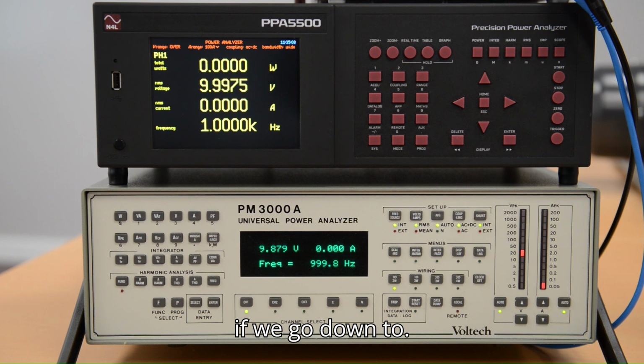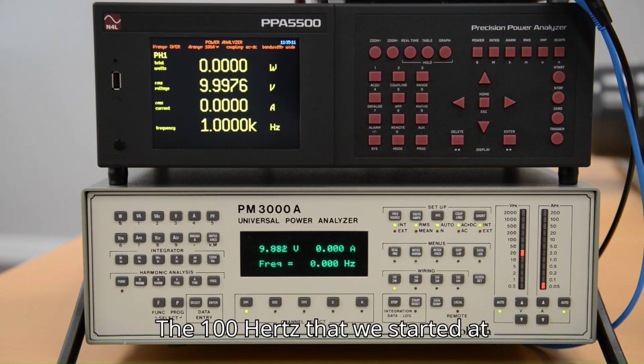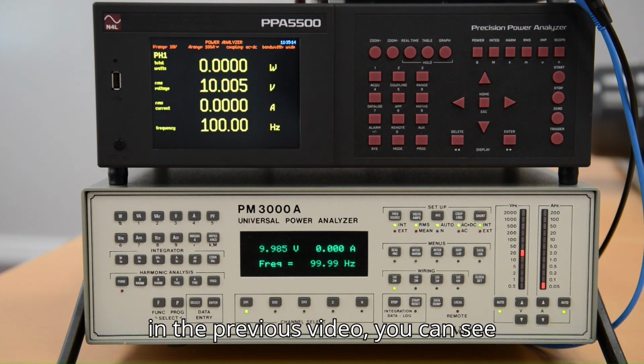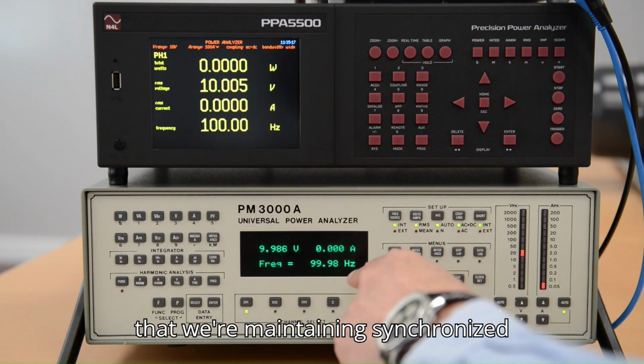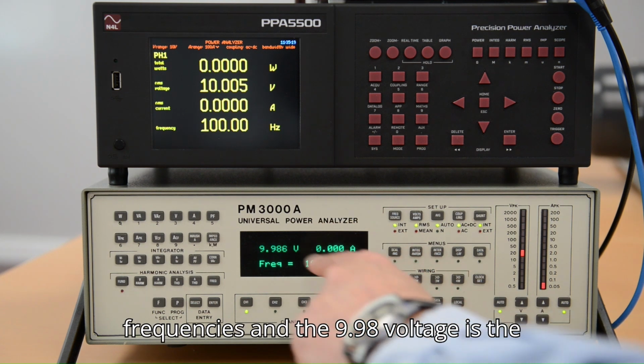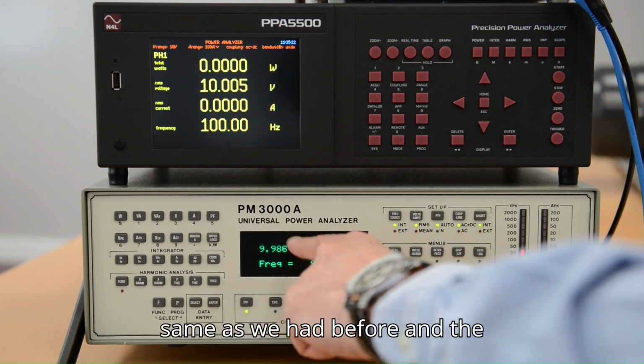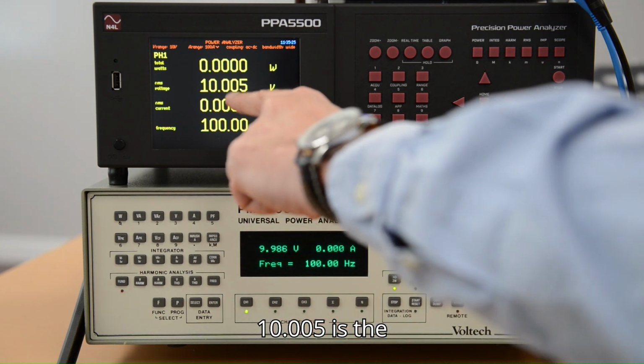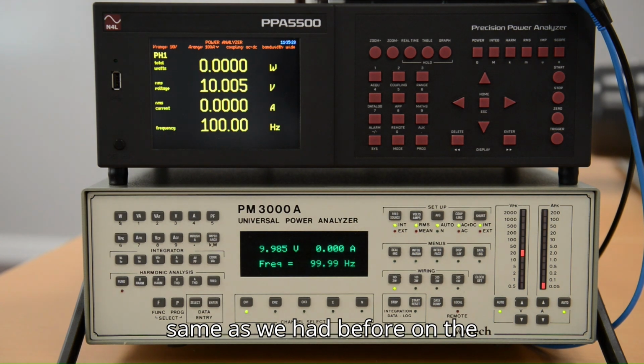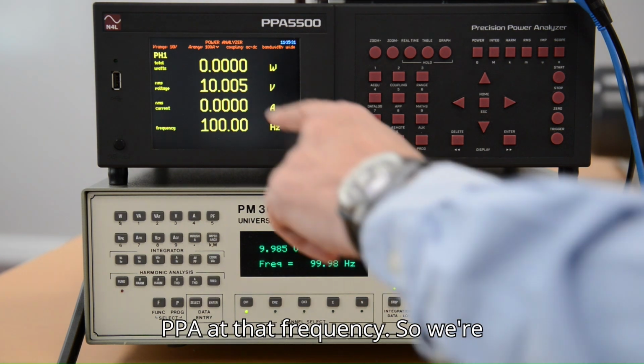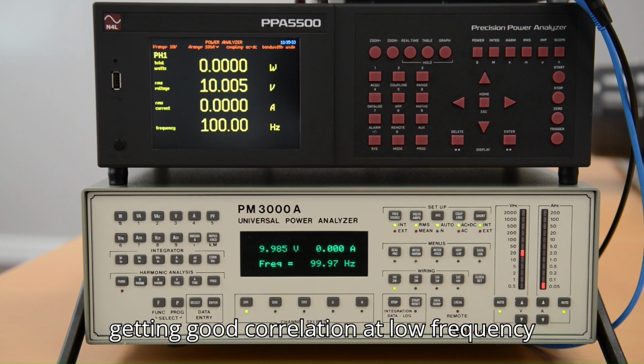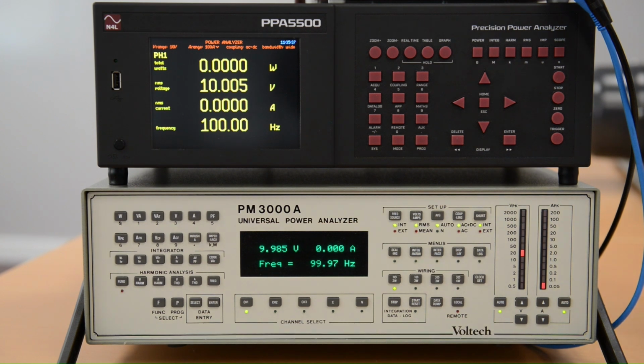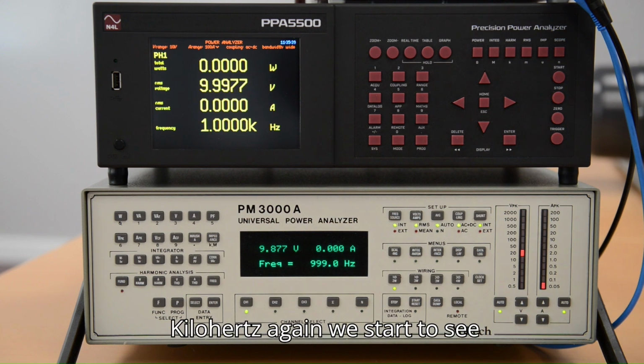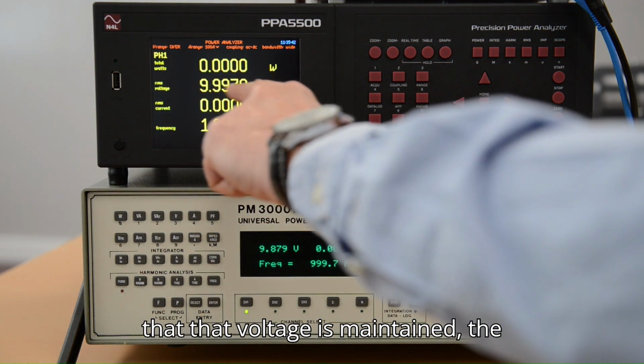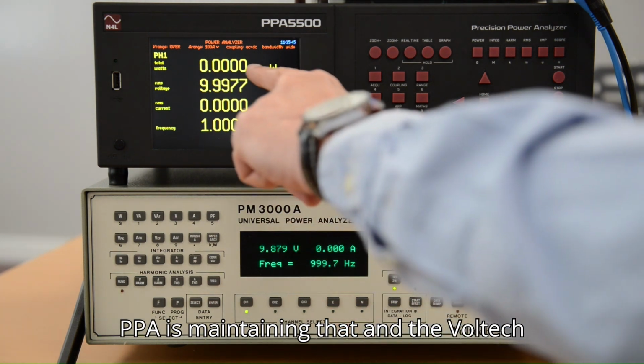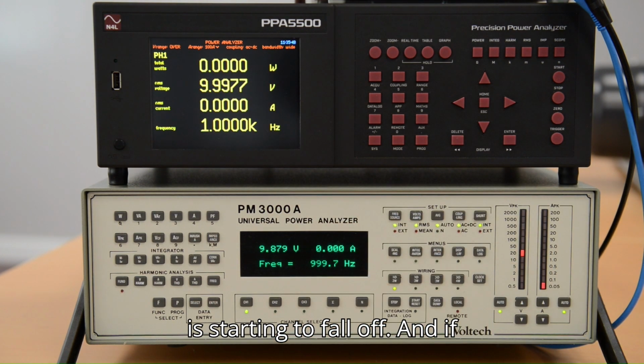Now if we go down to the 100 Hertz that we started at in the previous video, you can see that we're maintaining synchronized frequencies, and the 9.98 voltage is the same as we had before, and the 10.005 is the same as we had before on the PPA at that frequency. So we're getting good correlation at low frequency. And when we go up to a kilohertz again, we start to see that that voltage is maintained, the PPA is maintaining that, and the Voltech is starting to fall off.